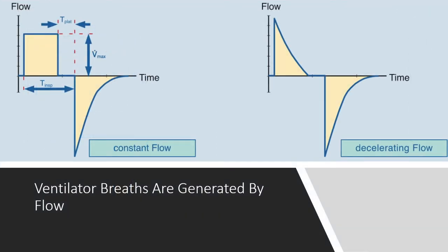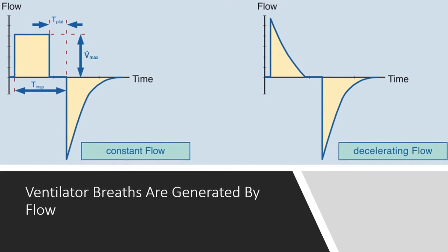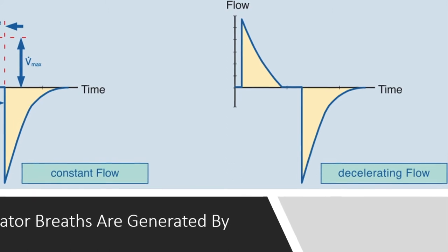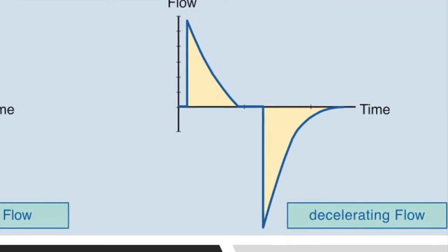This contrasts with pressure ventilation, which produces a decelerating flow. In decelerating flow, you start off with a very high flow rate which then drops over time — a very high flow rate to get you to the preset pressure, then you need less flow to keep it at that preset pressure until flow drops to zero. This is still inspiration, then you cycle into expiration. The advantage of the decelerating flow breath is that for the same mean airway pressure, the peak inspiratory pressure will be lower.